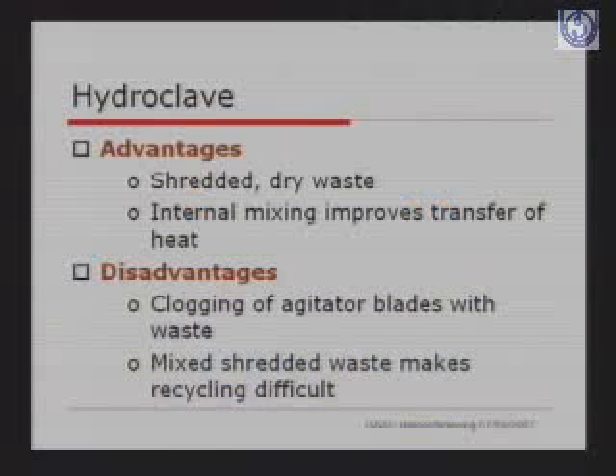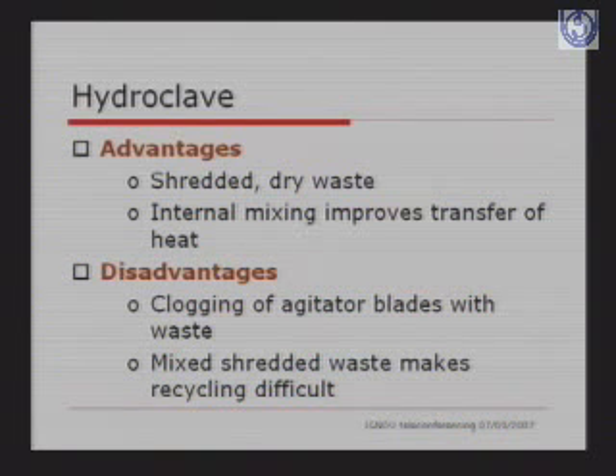Internal mixing improves transfer of heat within the waste. But the other disadvantage here is that the recycling value of the waste really goes down, because the entire waste is mixed inside, and so it cannot be recycled. The other option is we just send well segregated waste into the hydroclaves, so if one cycle is for the syringes, the second cycle goes for the cottons and all, and the mixing doesn't happen. And then there are frequent chances where the blade gets clogged.